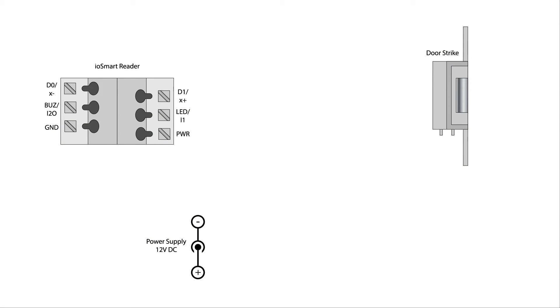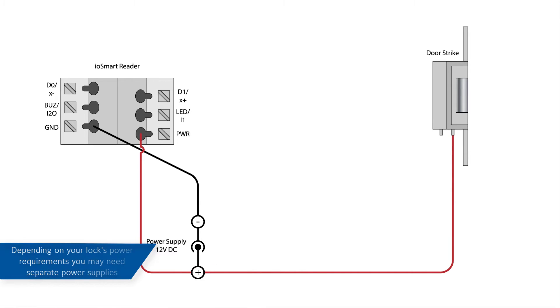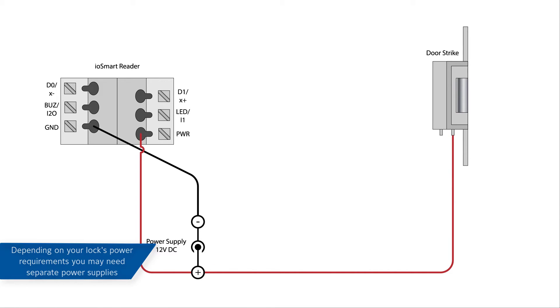Connect the 12-volt power supply ground to the ground terminal of the reader. Connect the power supply's positive to the power terminal of the reader. Connect an appropriate power supply positive to the lock terminal. This illustration shows both the reader and the lock powered by the same power supply.